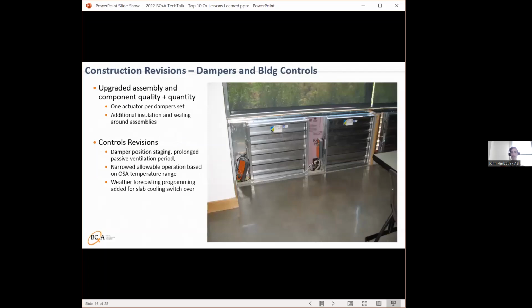So we ended up fixing this by doing individual damper sets, higher quality leakage class, higher torque, and making sure that we set the close position correctly, with just a little additional torque at the very end to close it. So it's just a matter of setting that damper end stop to have a little bit of pressure, but not too much, to not hurt the longevity of the actuator. Additional insulation: we found poor sealing and missing insulation around some of these damper sets. So they used rigid foam and tried to stay away from any spray foam, so that stuff could be removed and replaced if necessary.